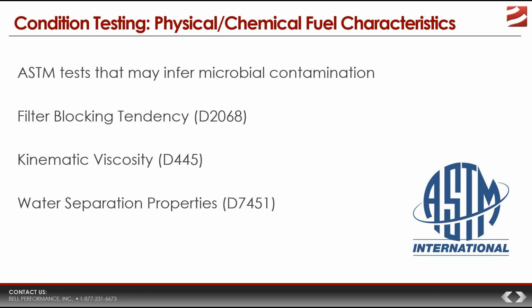Filter blocking tendency. This measures the particulate load that's present in a fuel. And if you have microbial contamination right now, you will have a higher particulate load, right? There's kinematic viscosity, D445. It is important to verify the viscosity of any kind of fuel because viscosity plays an important role in things like is it going to be injected properly?